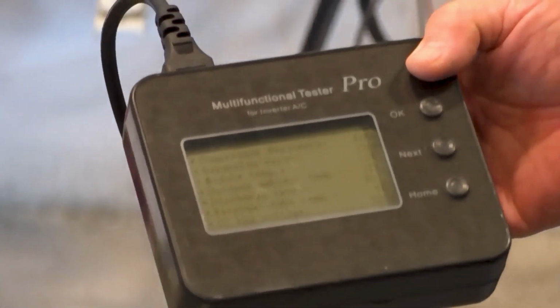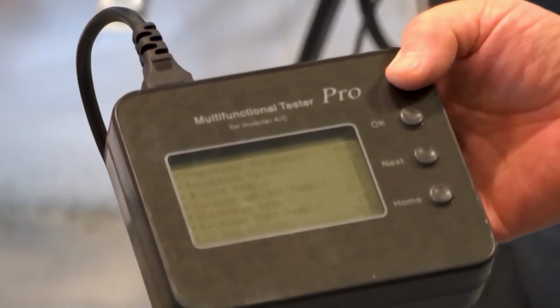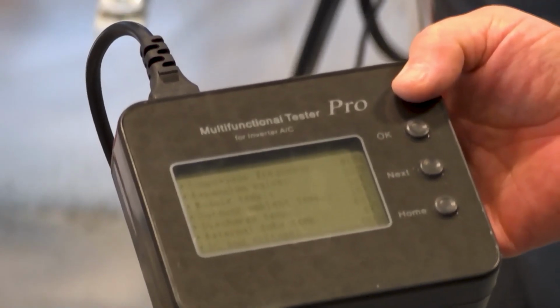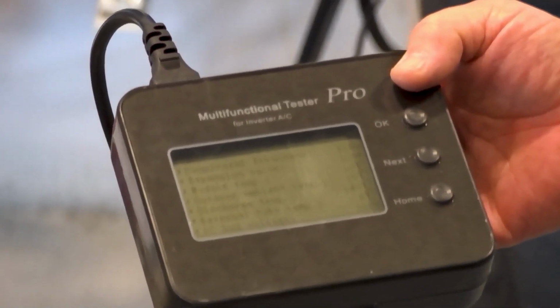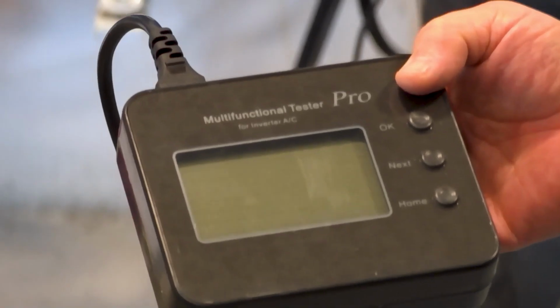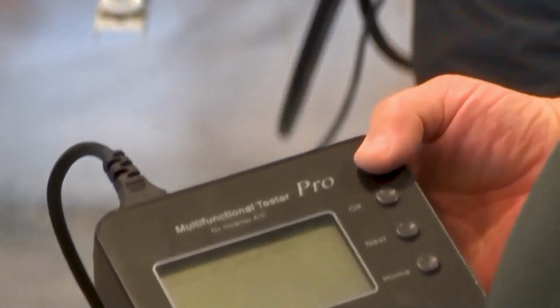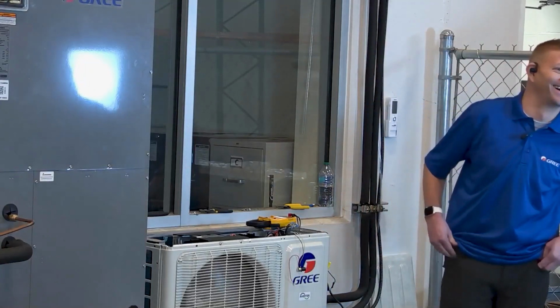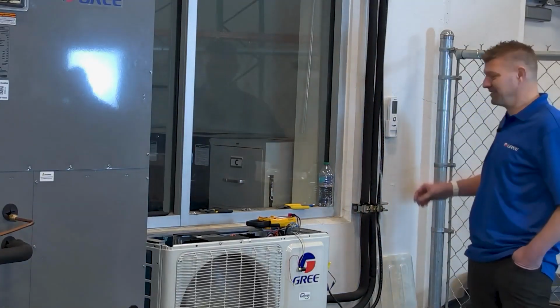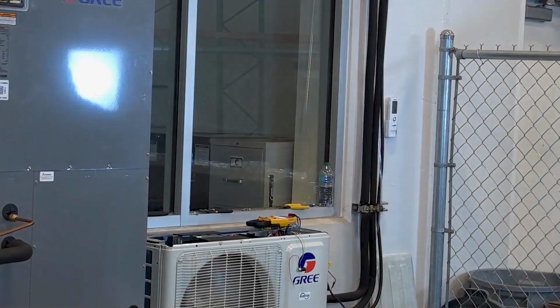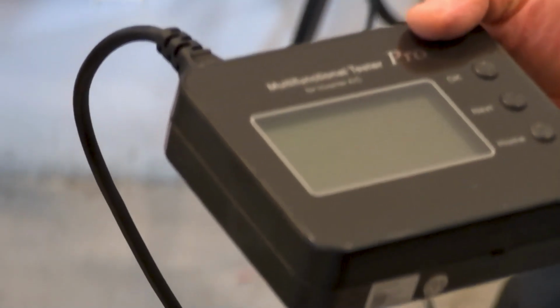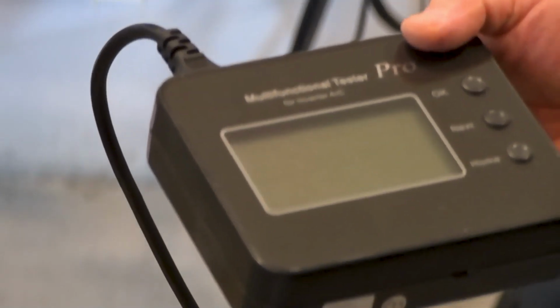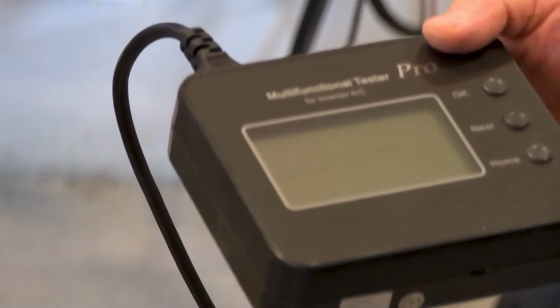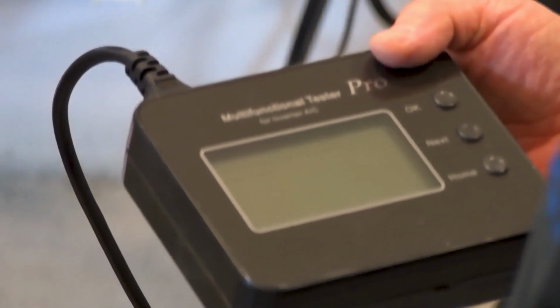So we're going to go ahead and increase it some more. So right now we're at 63 degrees Celsius. That's maxed out. And we're, well, not that much, back it off. Oh, back it off. It might be too late. It coded out. Man, it did it quick. So it just went out on high discharge temperature. And if we wait long enough, the display on the unit should actually give us the fault as well. I'm going to wheel it back. No, leave it up. Okay. I want to let it go ahead and fault out at this point.